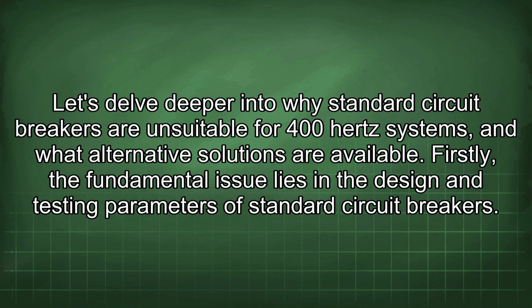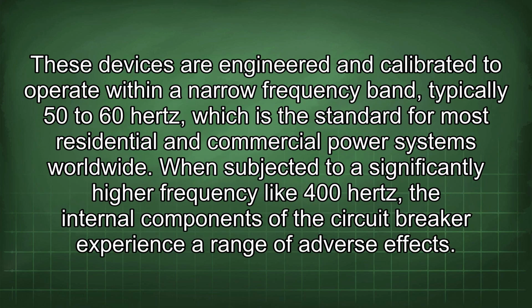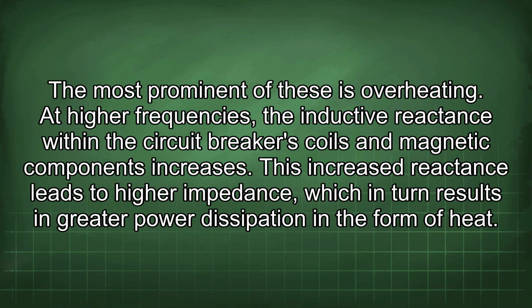Firstly, the fundamental issue lies in the design and testing parameters of standard circuit breakers. These devices are engineered and calibrated to operate within a narrow frequency band, typically 50 to 60 Hz, which is the standard for most residential and commercial power systems worldwide. When subjected to a significantly higher frequency like 400 Hz, the internal components of the circuit breaker experience a range of adverse effects. The most prominent of these is overheating.